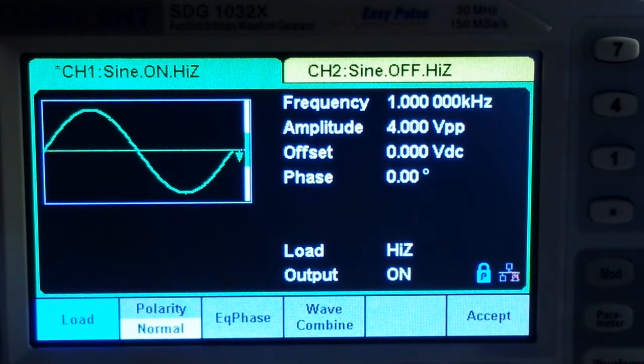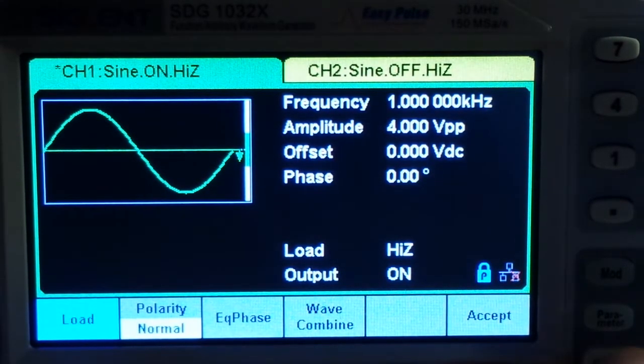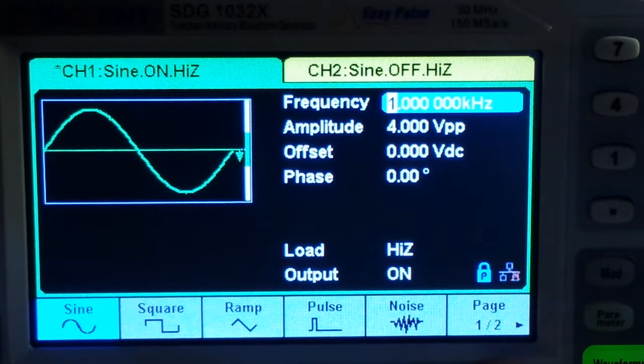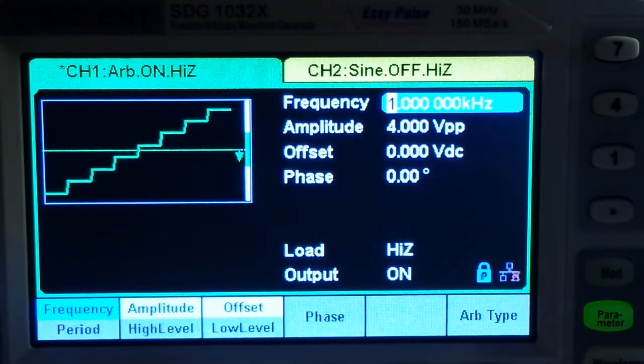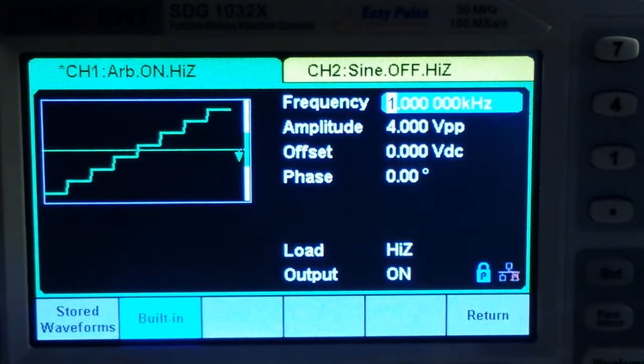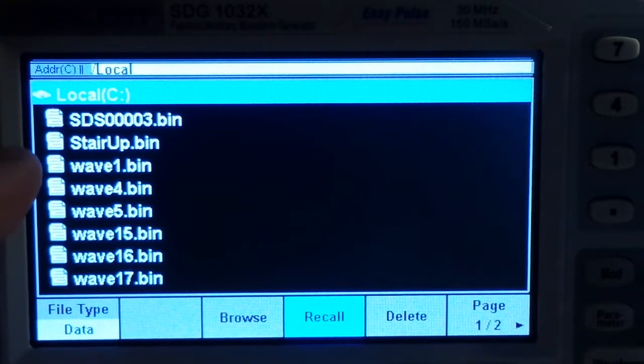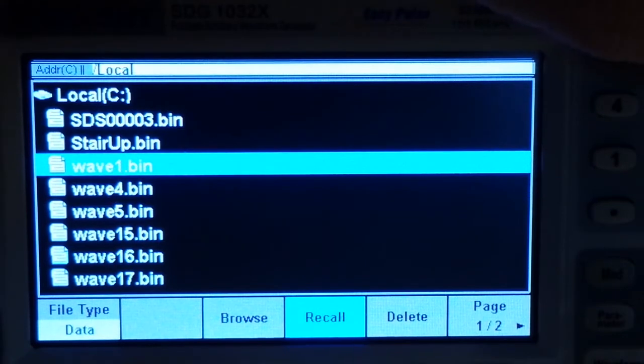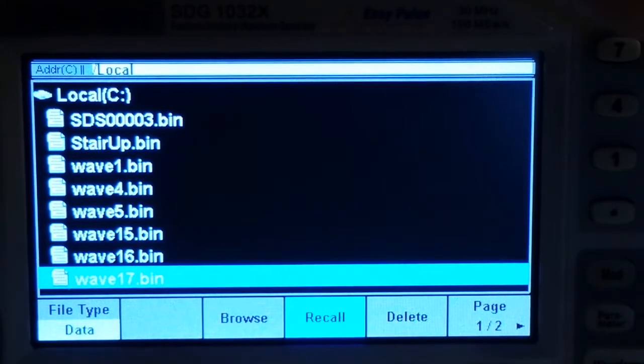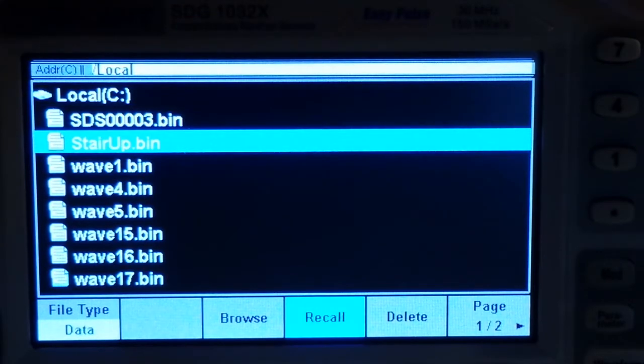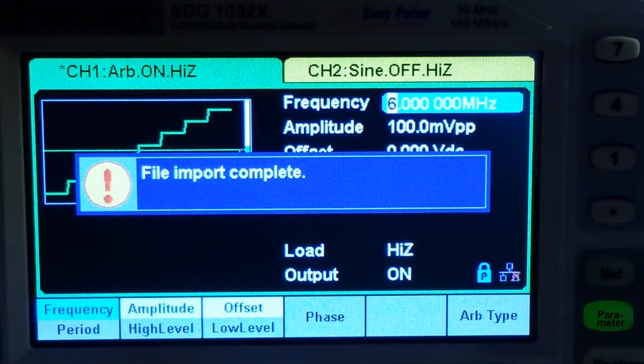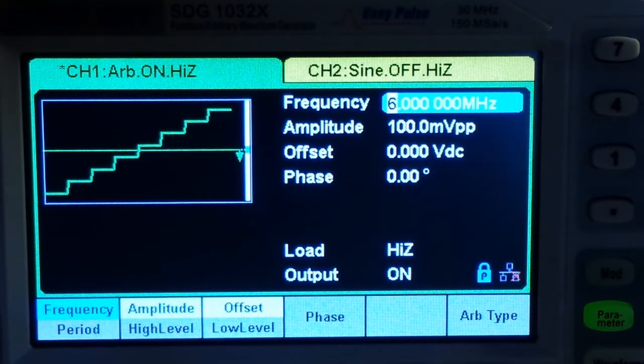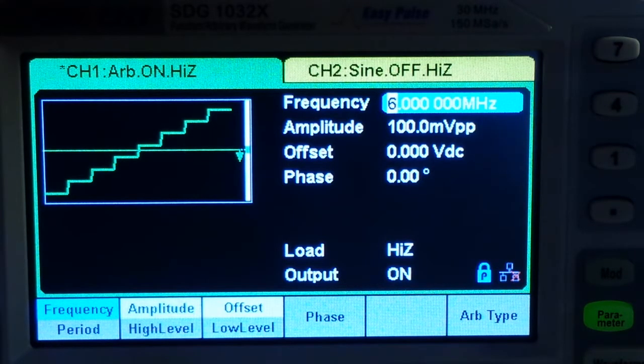Now one of the other last things I want to touch on is the fact that you can create and load your own waveforms. If we come in here to our waveform, page two, arbitrary, arb type, stored waveforms. These are the ones that are stored on the hard drive. And we can select them with the multifunction knob. And there are quite a few of them. Here is a stair up. Click to select. File import complete. And you can see we have a 6 megahertz stair step with 100 millivolts peak to peak. Very nice indeed.